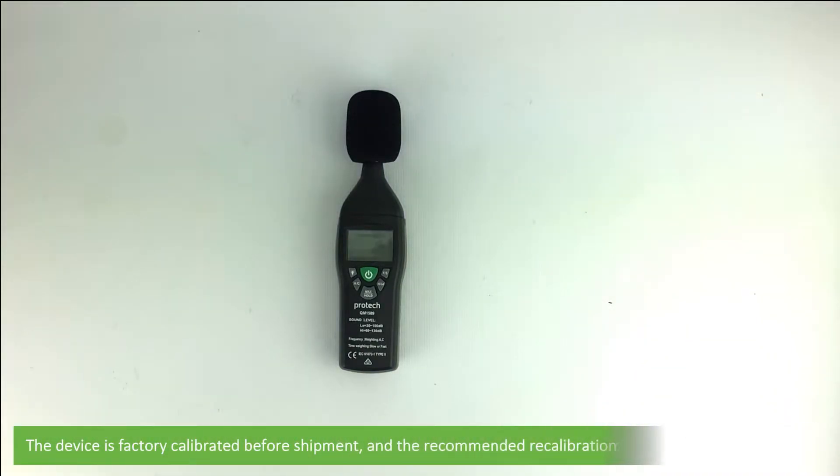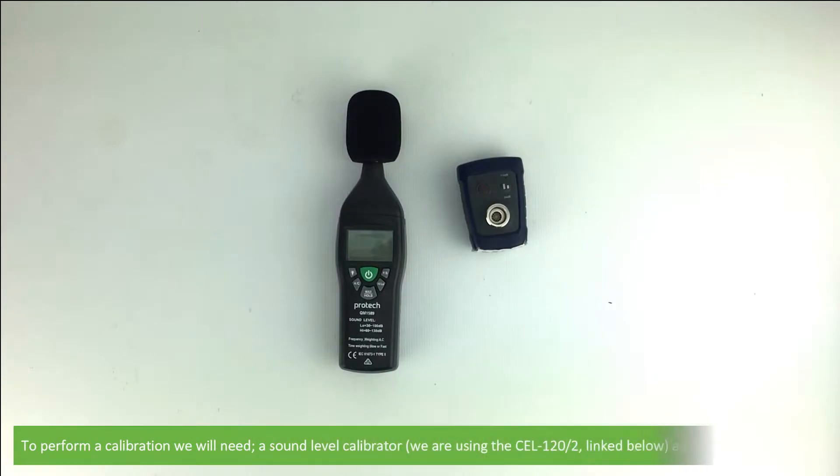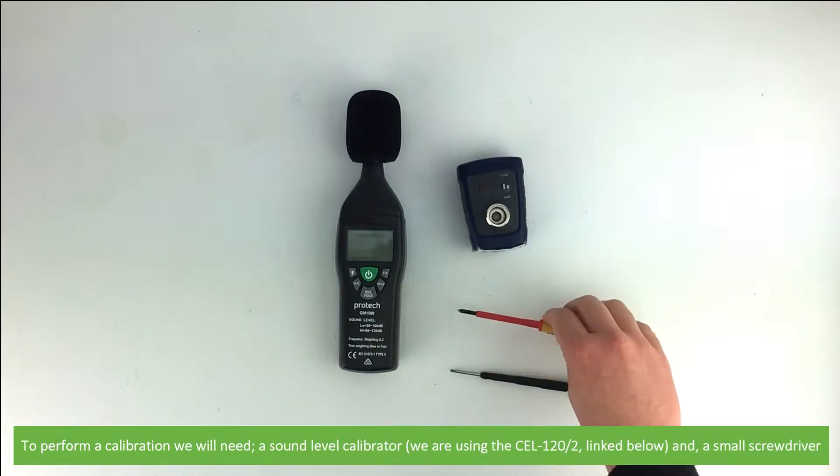The device is factory calibrated before shipment and the recommended calibration cycle for this device is yearly. To perform a calibration we will need a sound level calibrator, we're using the CEL 120-2, this is linked below, and a small screwdriver.